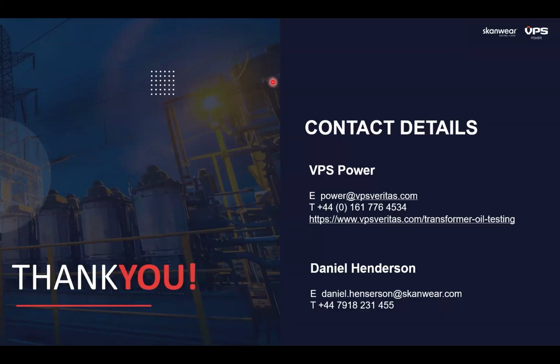I don't know if you want to mention anything on that, Dan, or any comments with that? Well, we can't do oil sample analysis in relation to that, but I think we mentioned it on the maintenance webinar last month. If you look at an oil filled asset or a fluid filled asset, maintenance is normally done at a frequency of around five yearly or determined by the conditions, but typically it's every 5 years.